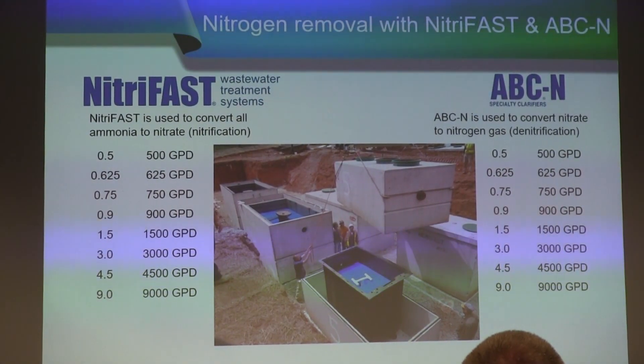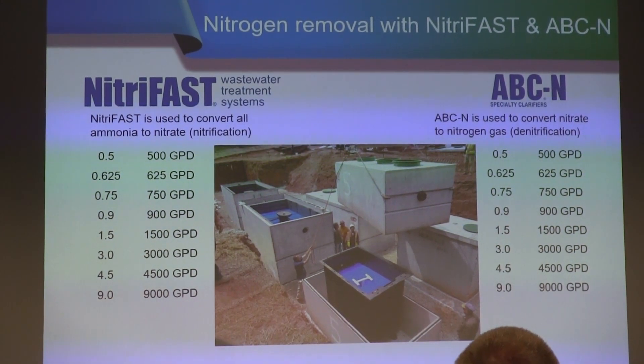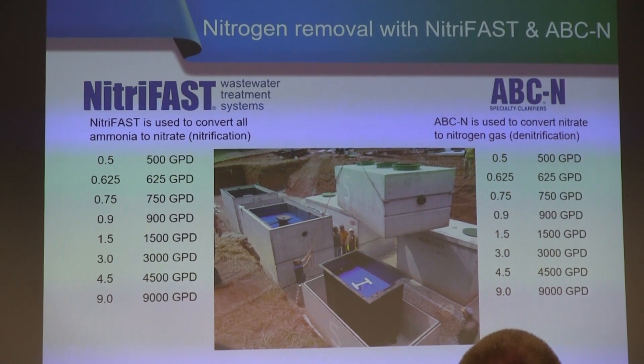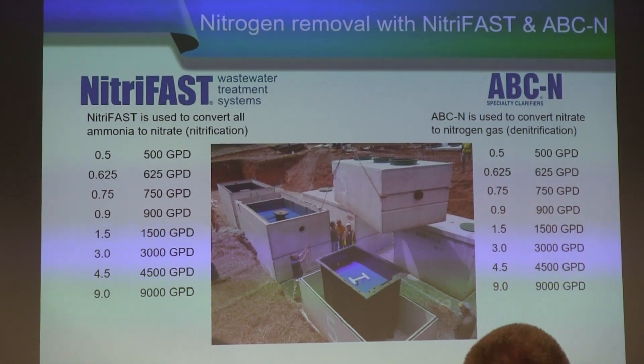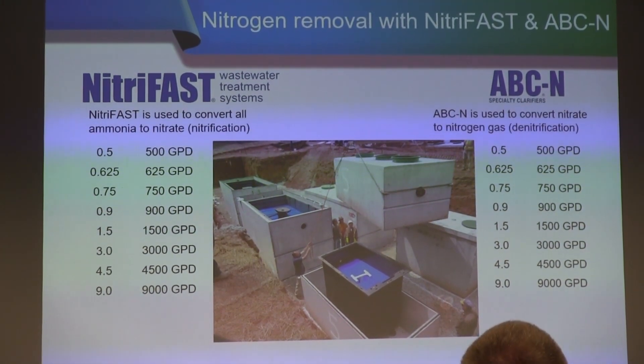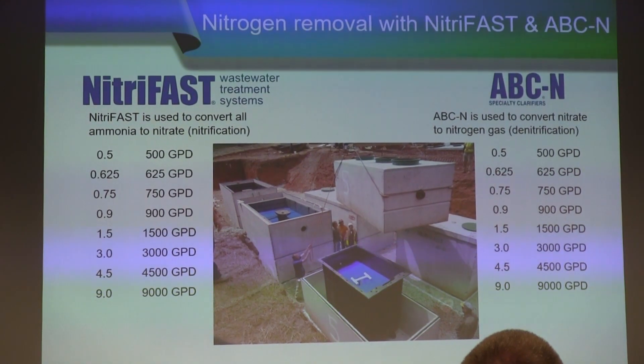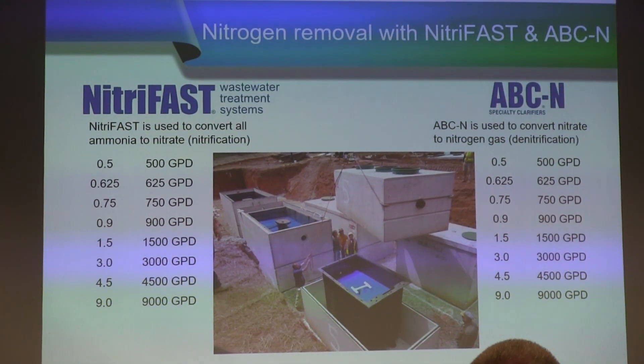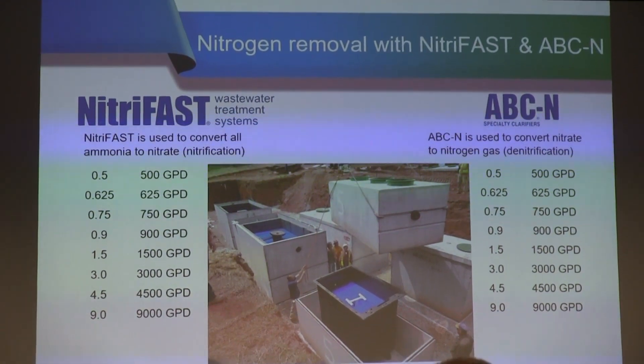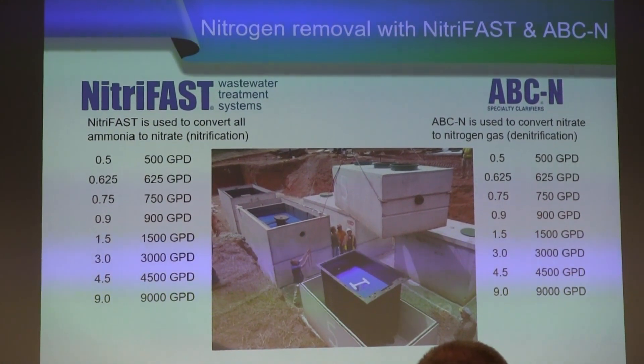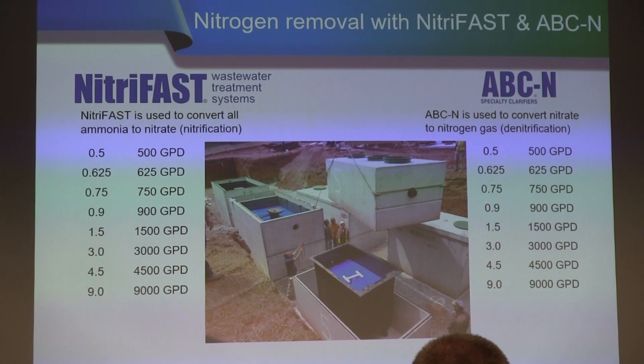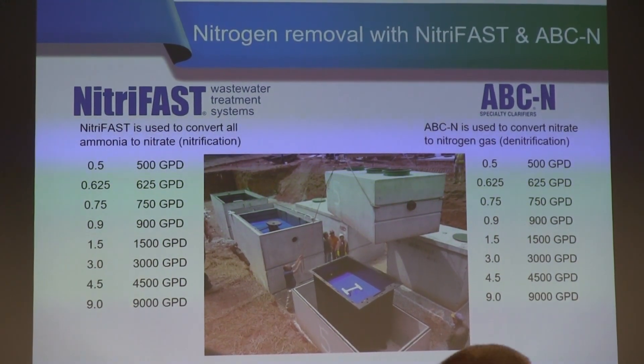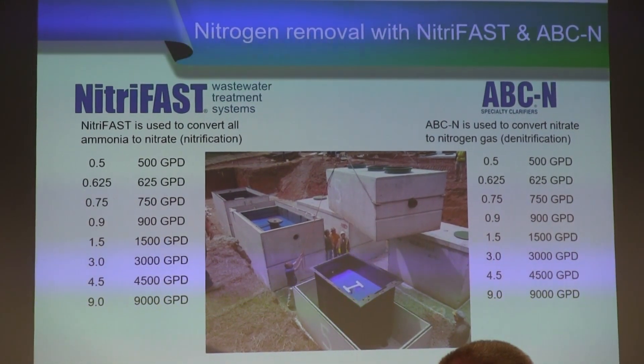A lot of times it's not just BOD and TSS that we're trying to remove. When you're looking at FAST systems, you also want to be able to treat total nitrogen. We have two products that we would typically follow a FAST system with — whether it's a Micro FAST or a high-strength FAST. When you really need to target a low total nitrogen number, we follow a Micro FAST or high-strength FAST with the NitriFAST system, which handles additional nitrification — the conversion of organic nitrogen and ammonia to an oxidized form of nitrogen, nitrate.